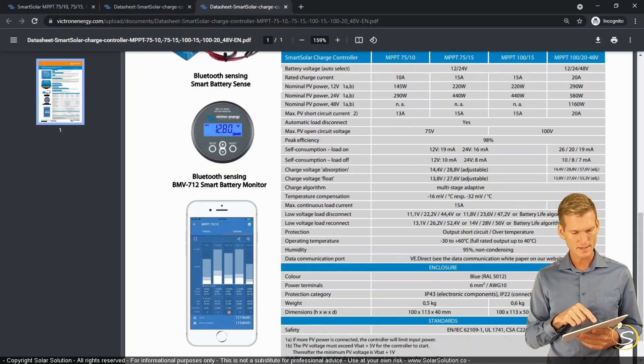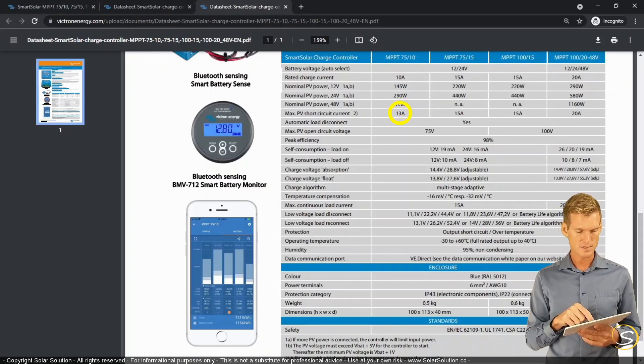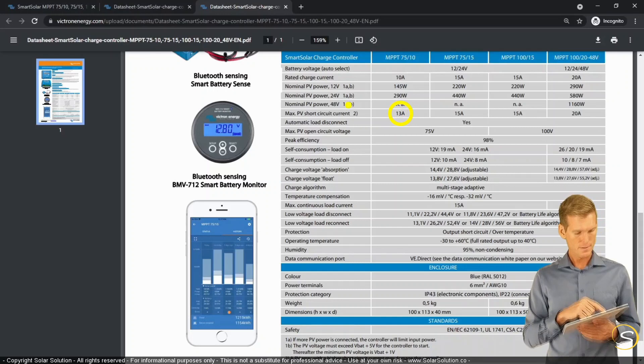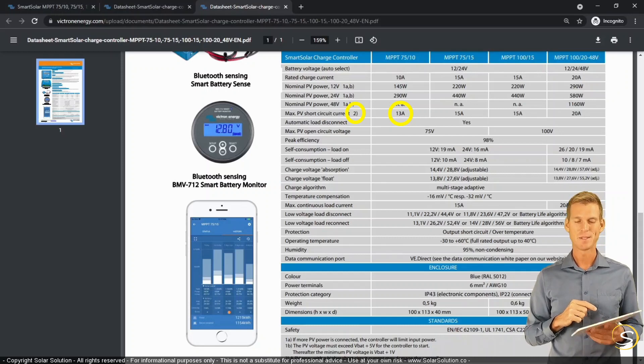So I just want to explain that. And then the other value, which is also really important, is the maximum PV short circuit current, 13 amps. And it places a note there as well, because if a PV array with a high short circuit current is connected to the system, it may damage the controller. So it will very likely break. So don't do that. That's a very bad plan.